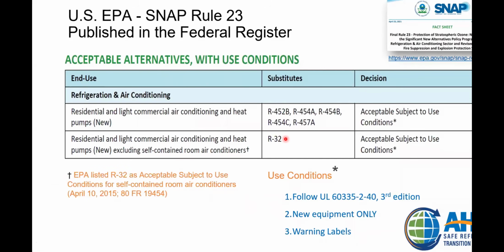R32, Daikin owns the patent on that. So Daikin's obviously very interested in using R32 instead of R454B. Additionally, Daikin already has R32 in Europe and other places. So for them, it's a matter of changing it from 50 hertz to 60 hertz power and importing it to the United States, right? So the Daikin family of products, which would be Goodman, Amana, and those folks, they're all going R32. Here at TEC, we have Gree stuff, as you guys probably know. Gree is R32, as are several of the foreign manufacturers. Right, so Gree's made in China, Gree's R32. Carrier, for very large condensing units and very small scroll chillers, also has R32. Trane has R32 in their very large condensing units.